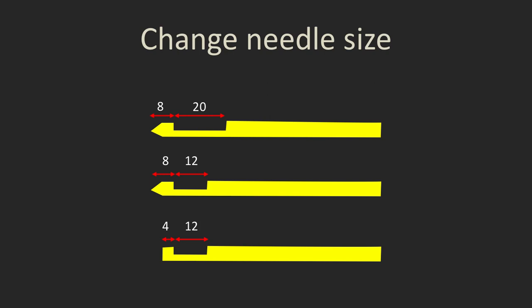Let's talk first of all about changing your needle size. Most manufacturers have at least two different needle sizes, if not three. I'm going to show you the specs for the Hologic needle, but they're also kind of similar. So the standard needle has a chamber size of 20 millimeters. And then there's about eight millimeters at the end beyond the chamber before the tip. You do have to account for that. That's going to be within the breast. You don't want that sticking out the other side of the breast.